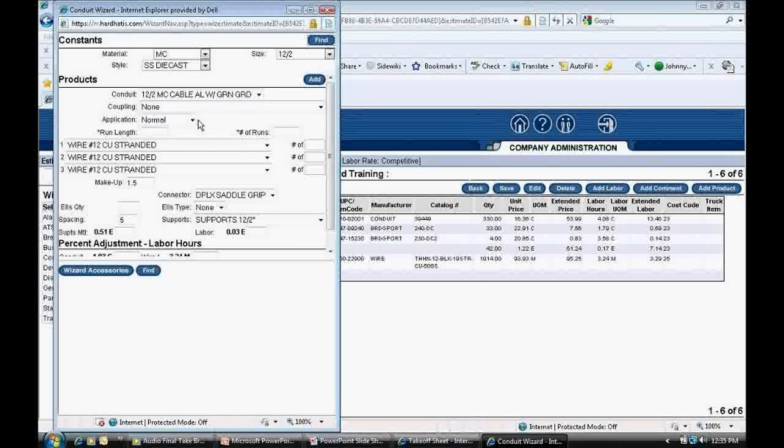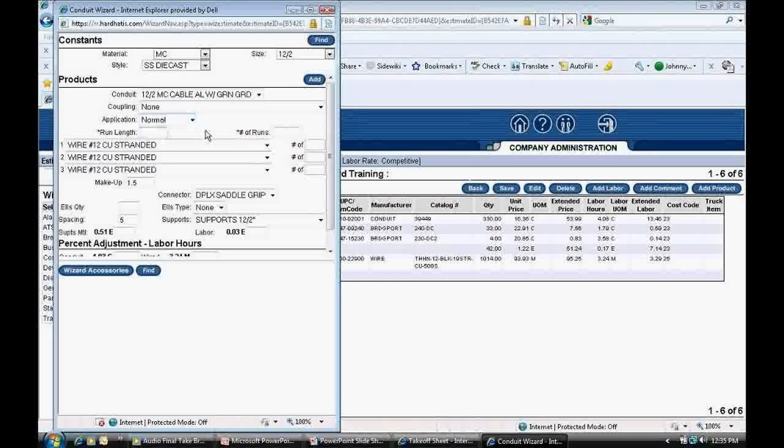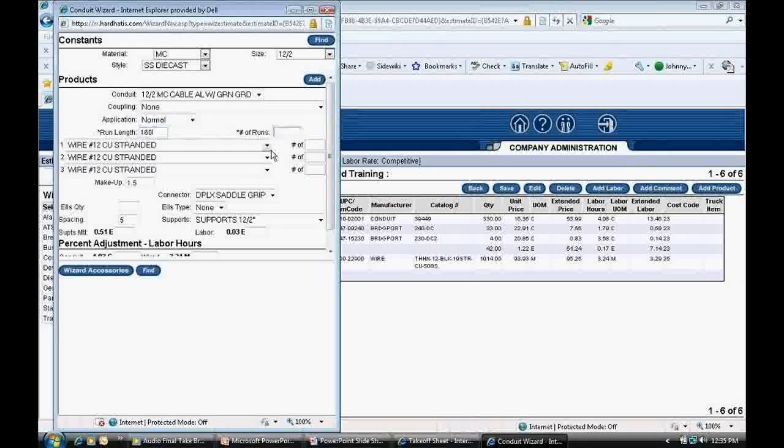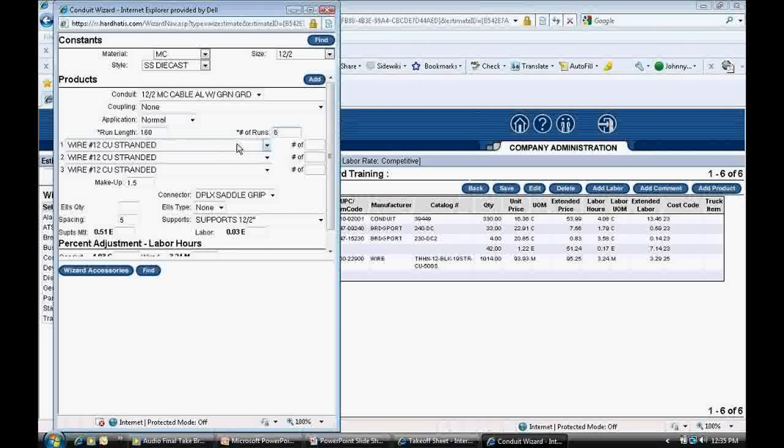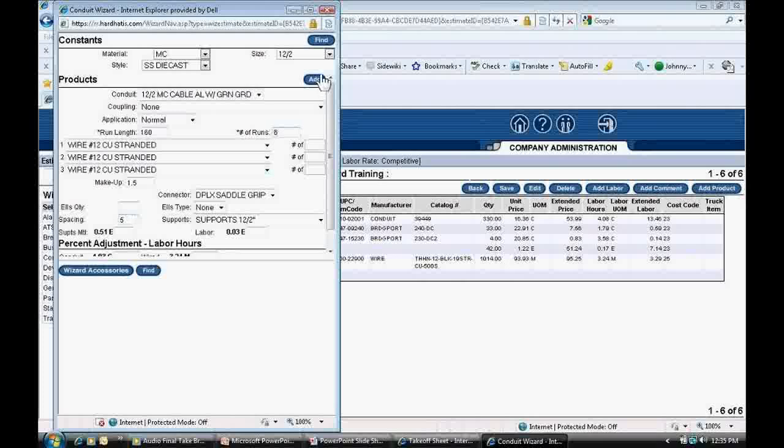Next, I will set the application. This time I set the application at normal because the MC cable is below 6 feet from the floor. Again, applications refer to how the conduit is to be installed. The program has additional labor built in for more difficult conduit runs. I click in the Run Length box and type 160 for the total footage of MC cable. I click in the Number of Runs box and type in the number 6. I do not have to deal with wire drop-downs for sizing wire or with the Makeup box. I leave them as is. Note that the support default is set at 5 feet, so the program is going to add a support for every 5 feet of MC cable entered.